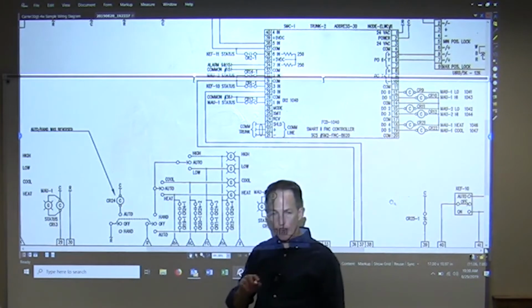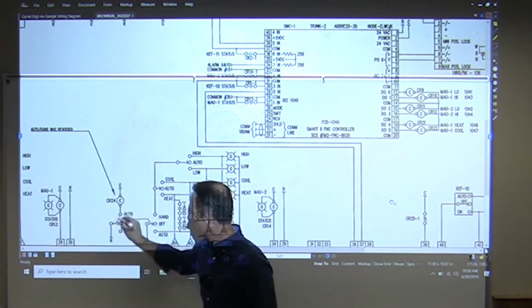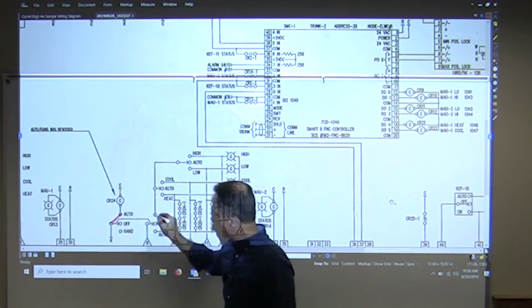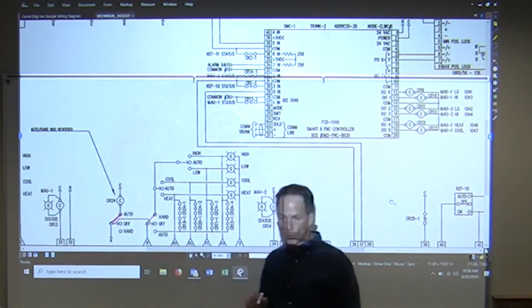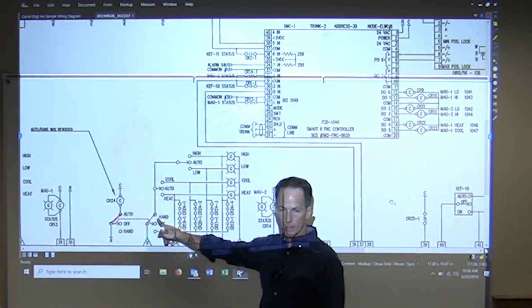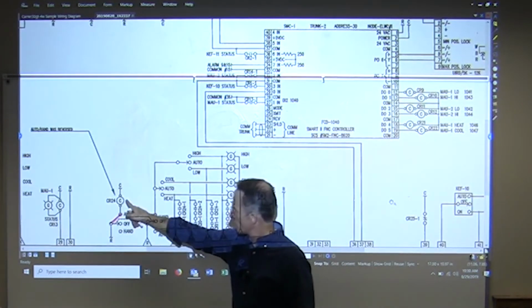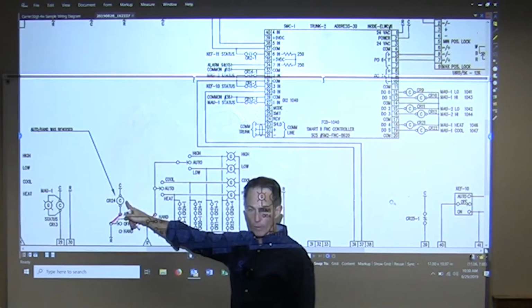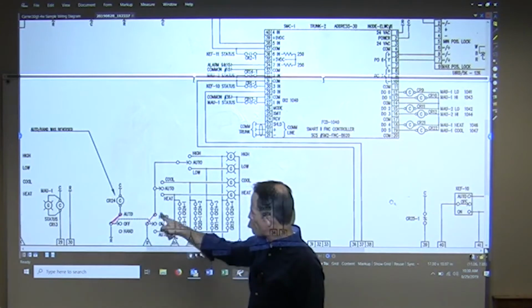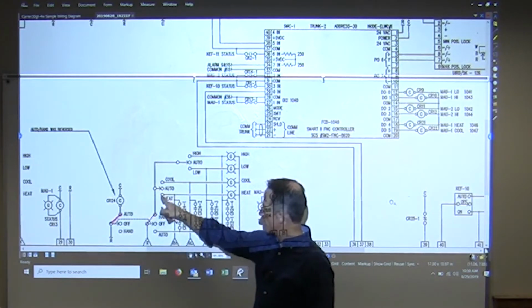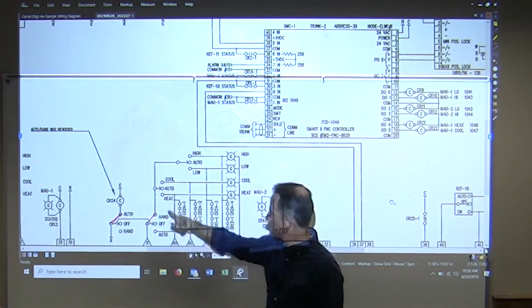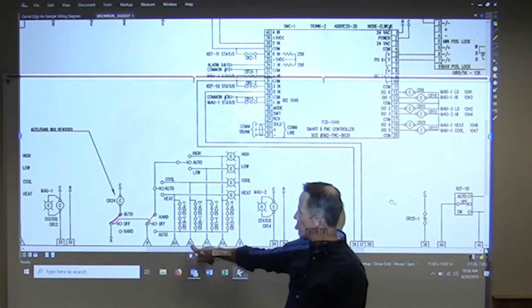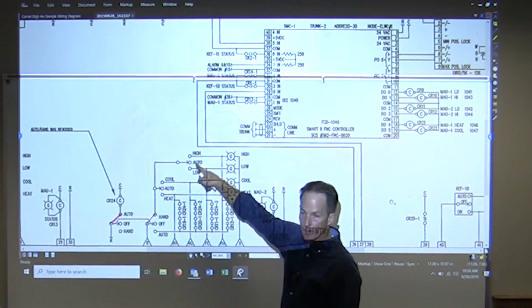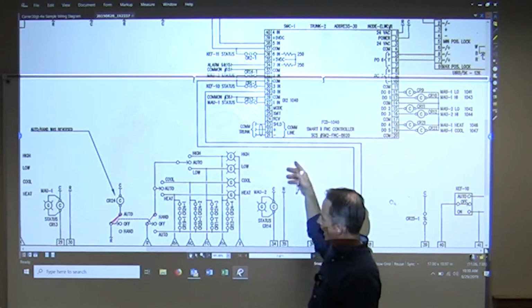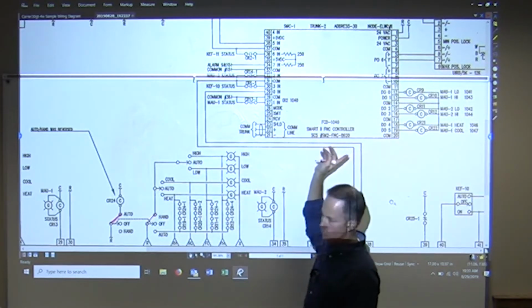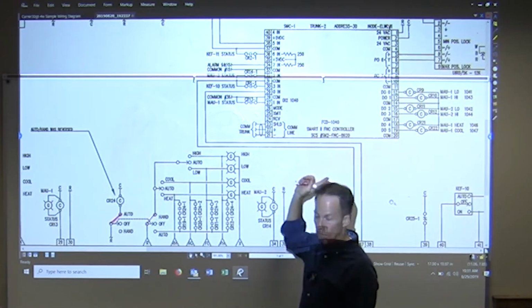Say for instance we were going to put this in auto and I go here. If this was normally the way that we represent it, then I would be here. So I've got 24 volts going to CR24, it energizes, and then I've got hand. Well, hand comes up here and I can go to heat, it turns on the heat. I go to cool, it turns on the cool. Or I can go to high and low speed off of this switch. But I have no way to control it using the auto function from the controller.